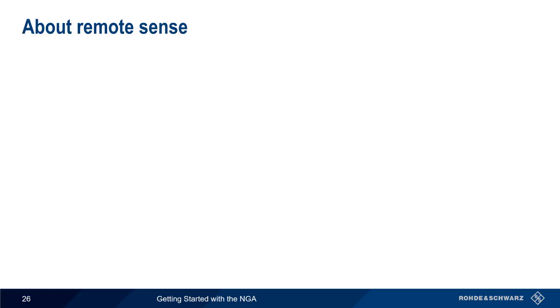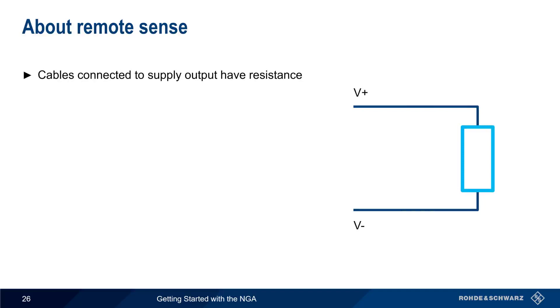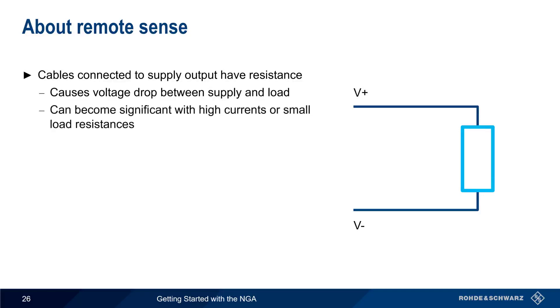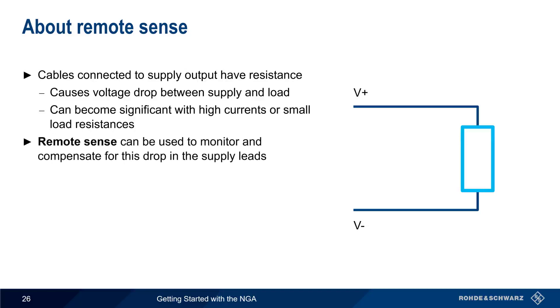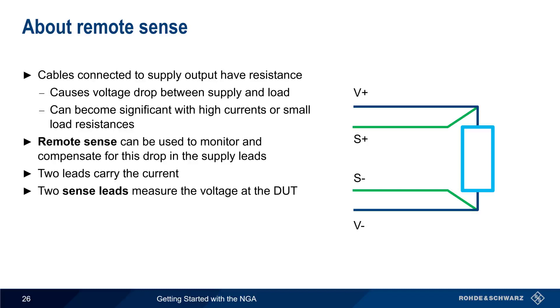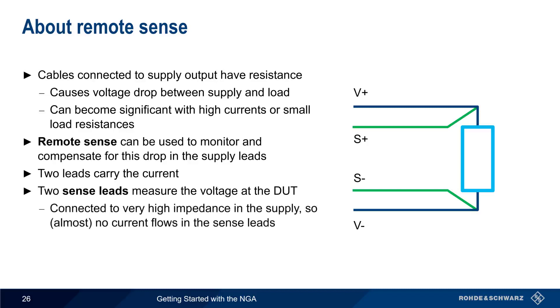The next topic is remote sense. The cables connected to a power supply's outputs have resistance, and this will cause a voltage drop between the power supply and the load. In many cases this very small drop can be ignored, but it can become significant with high currents or small load resistances. Remote sense is a method used to monitor and compensate for the voltage drop in the supply leads. In remote sense, two leads carry the current as normal, but two additional leads called sense leads are used to measure the voltage at the load. Because these sense leads are connected to a very high impedance in the supply, there's almost no current flow in these leads and therefore almost no voltage drop. Based on the readings made using these sense leads, the supply can adjust the output to obtain the desired voltage at the load.